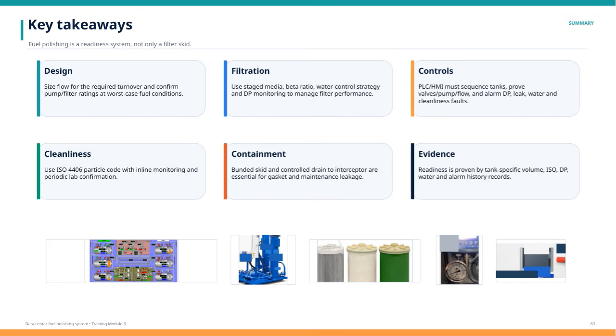In terms of filtration, it's best to use staged media, consider the beta ratio, implement a water control strategy, and continuously monitor differential pressure to keep the filters performing optimally. Controls play a crucial role as well. The PLC and HMI must manage tank sequencing, verify the operation of valves, pumps, and flow, and alert operators to any issues with differential pressure, leaks, water presence, or cleanliness faults.